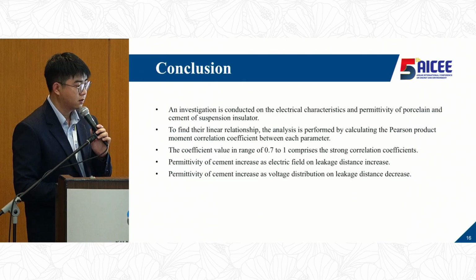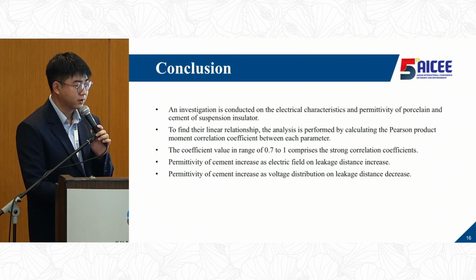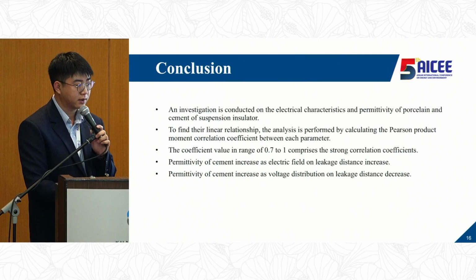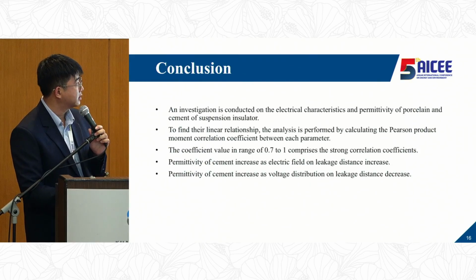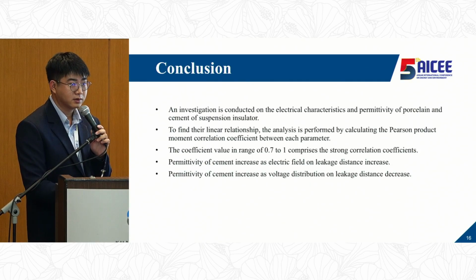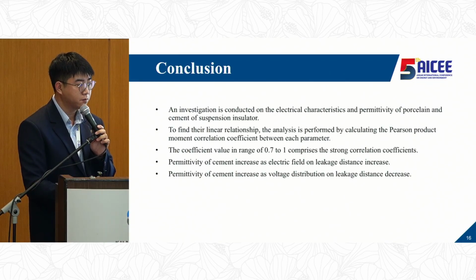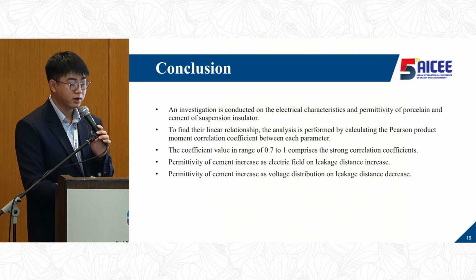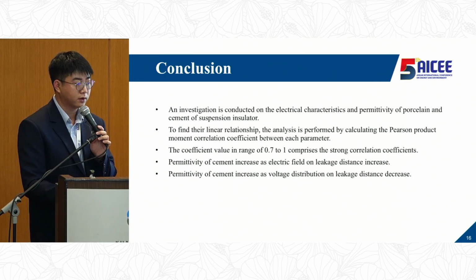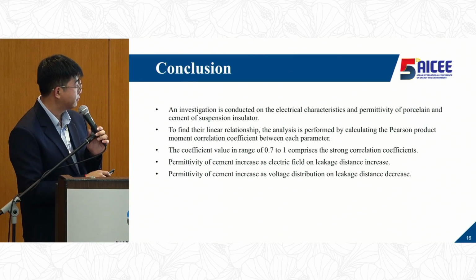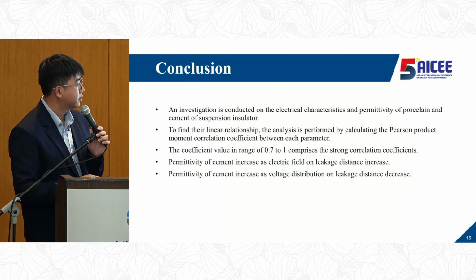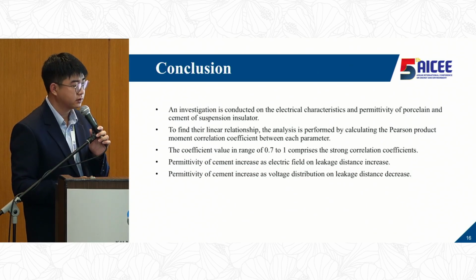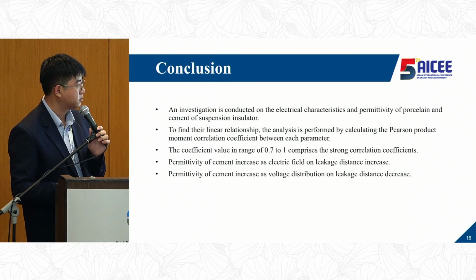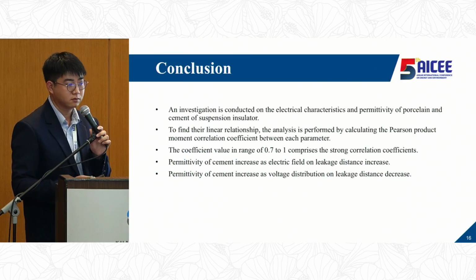To sum up my presentation, my research focuses on the electrical characteristics and permittivity of the porcelain and cement of the suspension insulator. To find their linear relation, the analysis was performed by calculating the Pearson product moment correlation coefficient between each parameter, with coefficient values ranked between 0.7 and 1, showing a strong linear relation. What I found is that as the permittivity of the cement increases, the electrical field on the leakage distance also increases, while the voltage distribution on the leakage distance decreases.